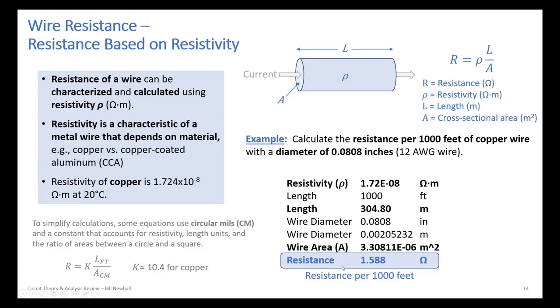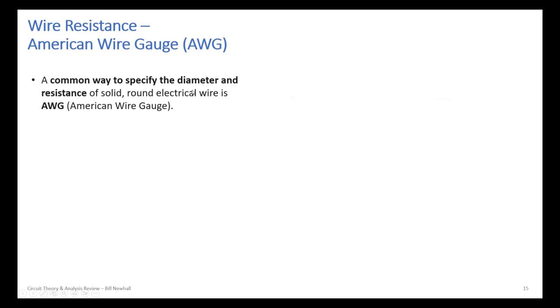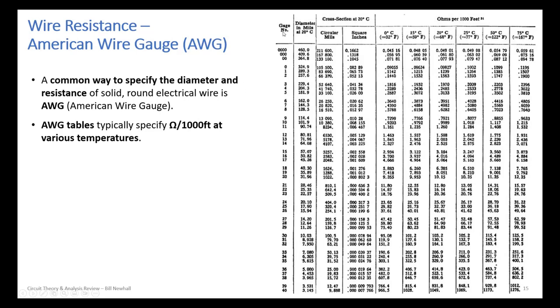Wires are usually not specified by diameter but by gauge. In the US, we use American Wire Gauge (AWG) — nobody says 'American Wire Gauge,' everyone just says AWG. AWG is the common way to specify the diameter and resistance of solid, round electrical wire. AWG tables specify ohms per thousand feet at various temperatures.